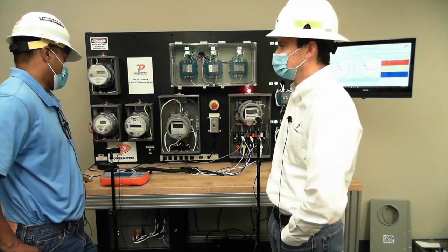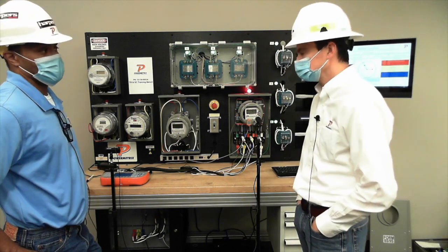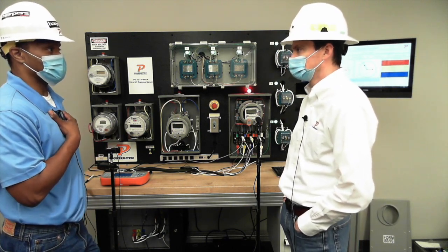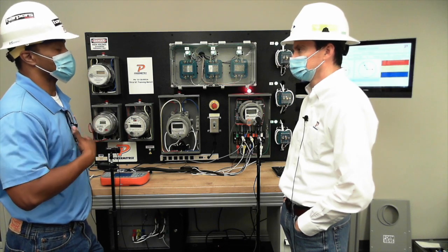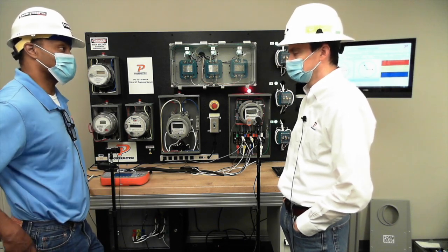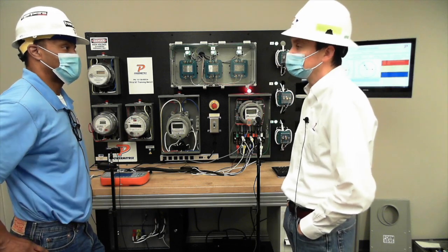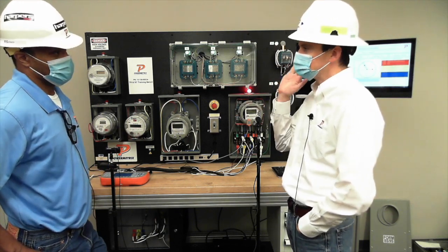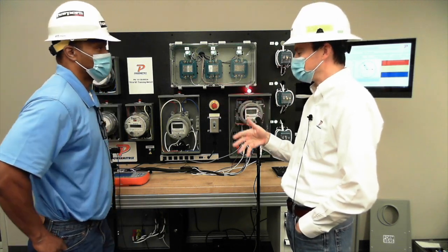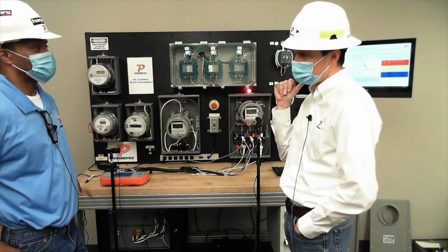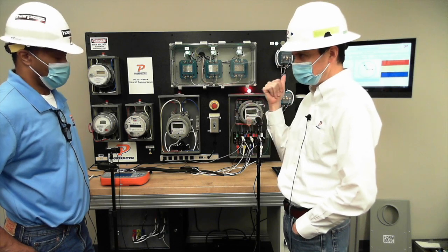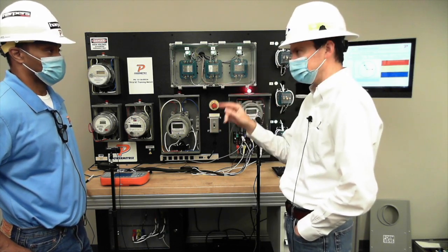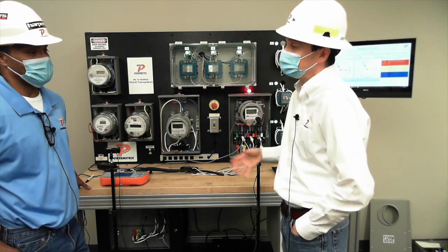But again, this does it both. If you ask me, did you test the meter? I can provide you with the meter testing results, and I can provide you with the demand testing results, all in one shot. So if you wanted to do all, what's the one I can do with the minimum amount of time? That would be a demand test, right? Because you got all of your basic test data. You got your meter test result, and you got your demand consumption all in one test. So yeah, a 15-minute test.